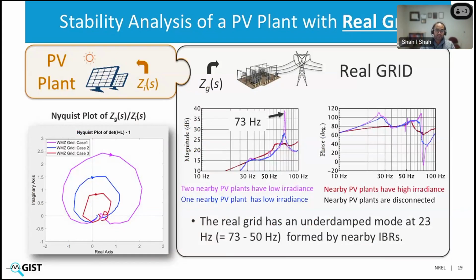So here I'm showing the impedance response of the West Murray Zone grid obtained from wide area system EMT model for 4 different conditions. And this is from looking from the POI of this particular PV plant. So the pink one is when there are 2 other PV plants in proximity which have low irradiance. And under that condition, we see that there is an underdamped resonance mode at 73 Hertz.